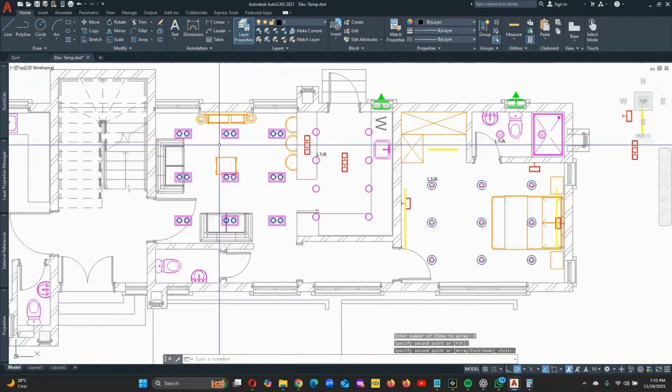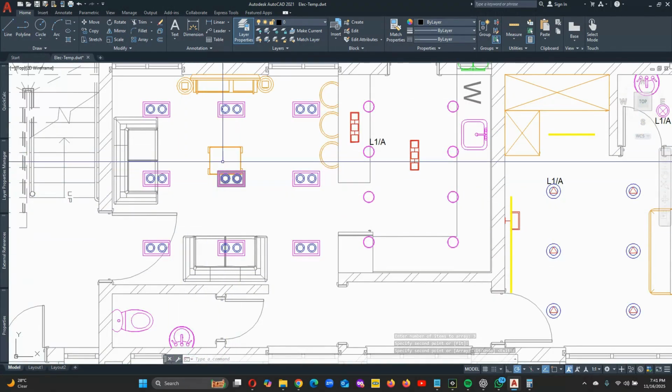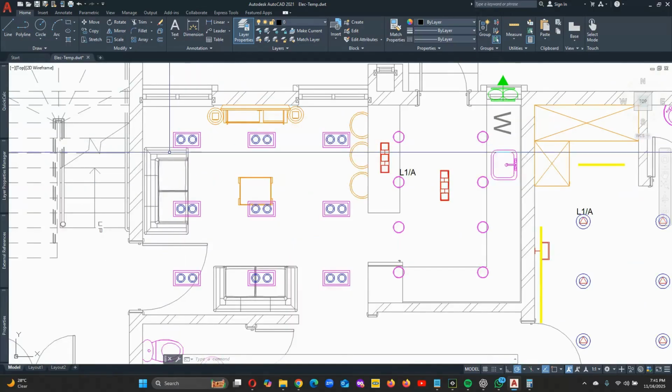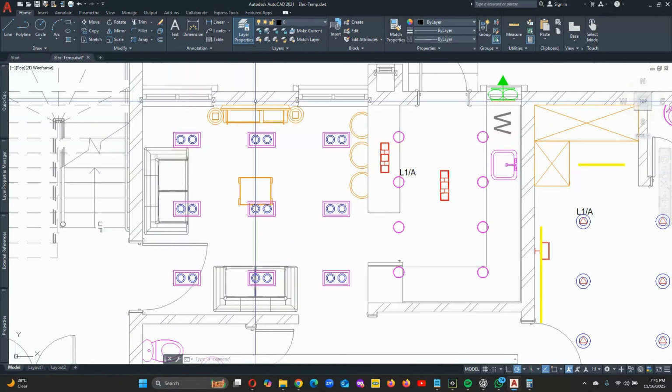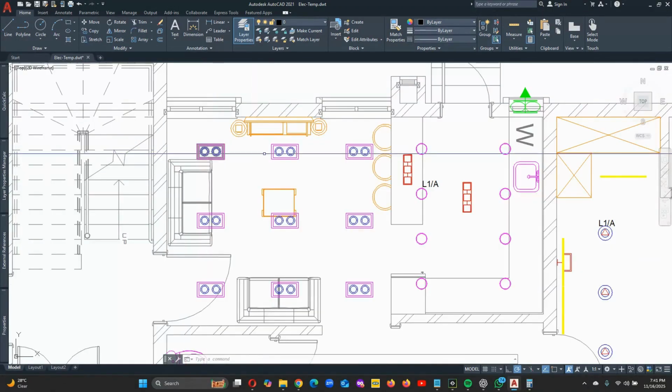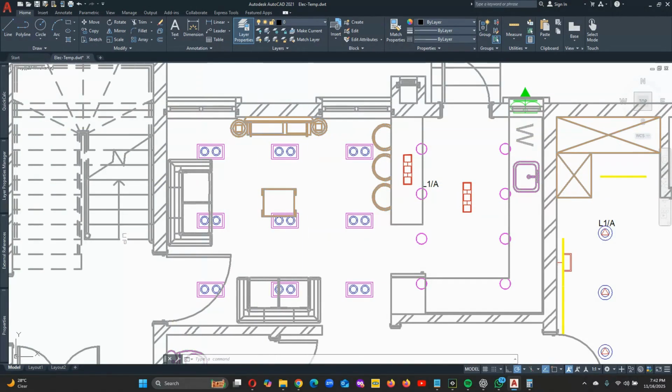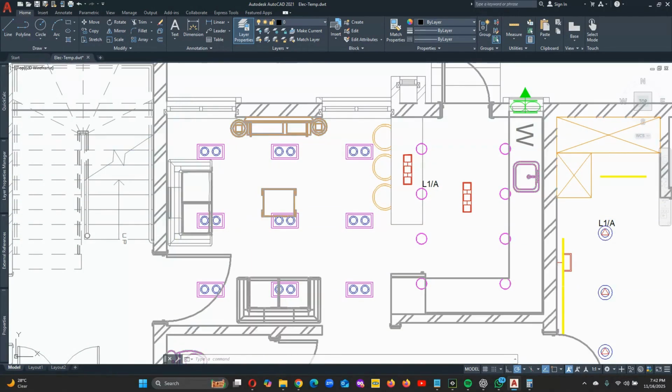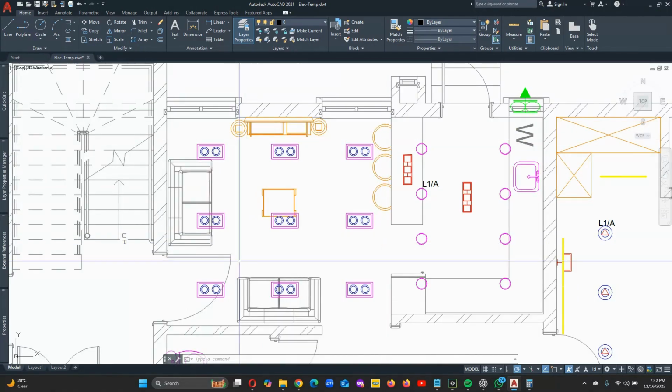So that's that. What are the things I want around here too? I want a chandelier here. I want wall brackets, one, two, and three wall brackets, and one chandelier. That's what I would like to have here. So this is the minimum required for lighting this area, 3 by 3, 9 watts. I'm using 2 by 4.5 watts each here, recessed down lights. Then I'm going to add three wall brackets, one here and one here. Then I'm going to add a chandelier and some LED strip lights, whichever way I want to do it.